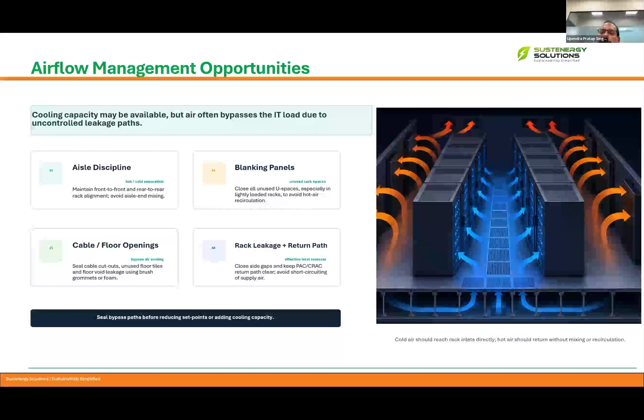The third area is floor and cable openings. We need to seal the cable cutouts because air escapes from that area also. Sometimes there are unused floor tiles, which should be properly sealed. They should not be perforated ones; they should be closed ones, so that we can avoid the leakage. Then we have to avoid rack leakage and keep the return path clear. We have to close the side gaps and keep the PAC and CRAC return path clear to avoid short circuiting of the supply air. These are some of the steps we can take for proper airflow management in data centers. We have to seal the bypass paths before reducing the set points and adding cooling capacity. That is the key takeaway from this.